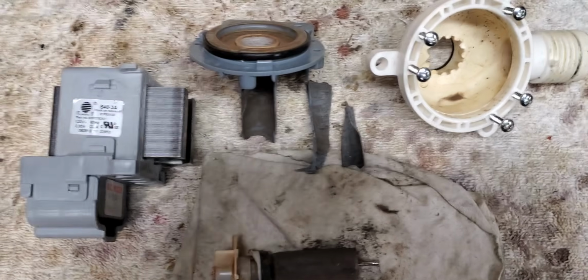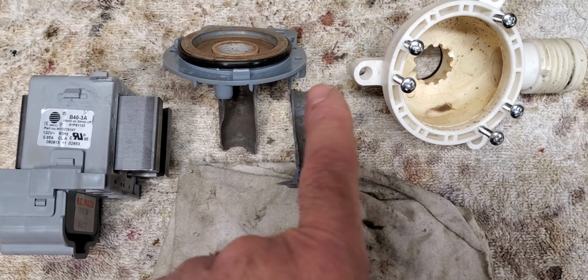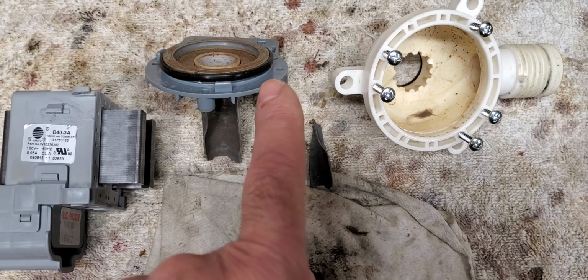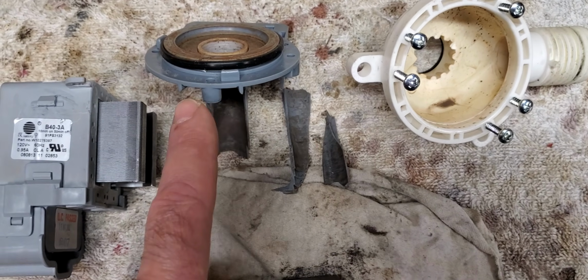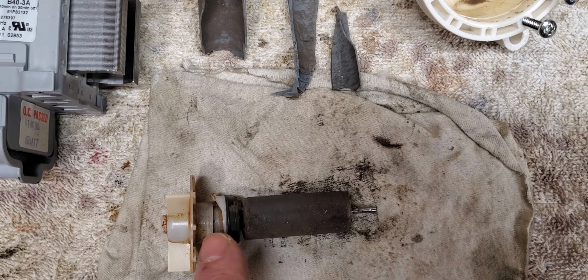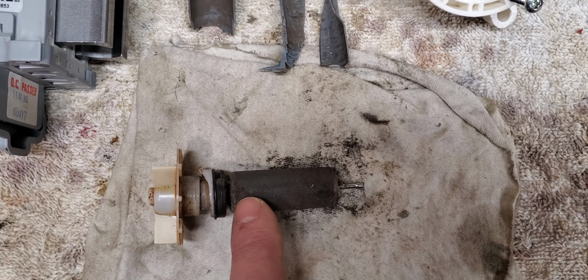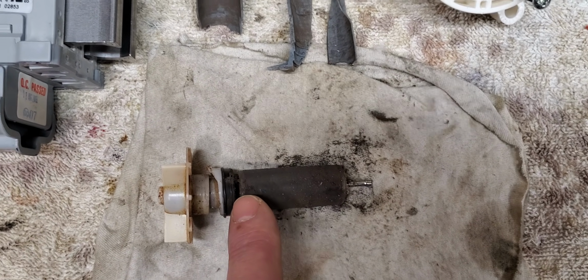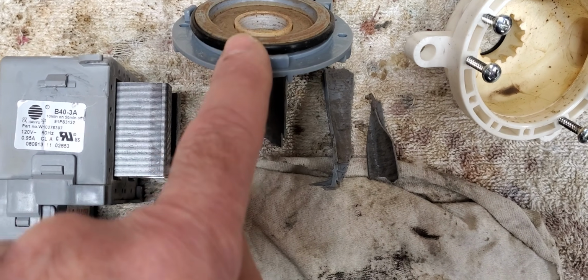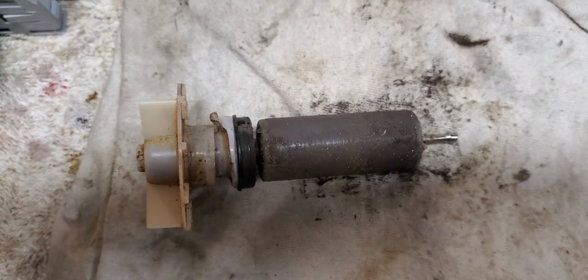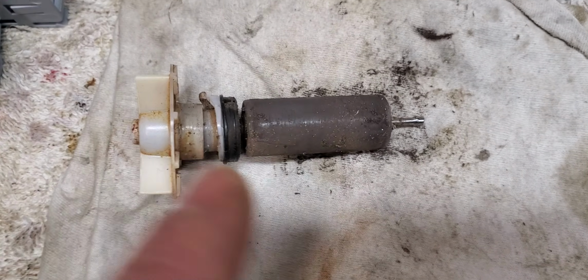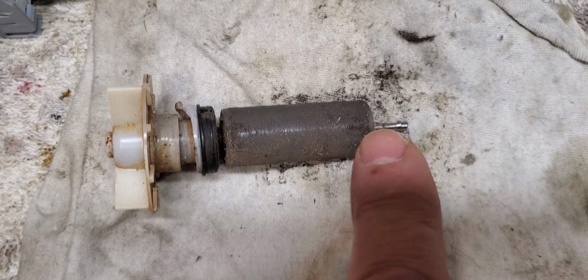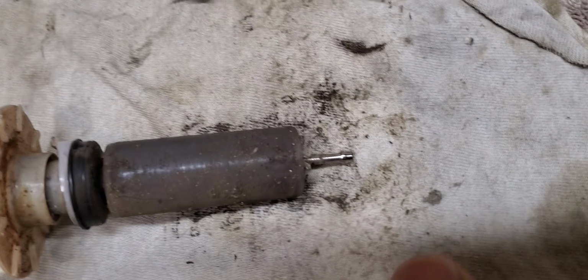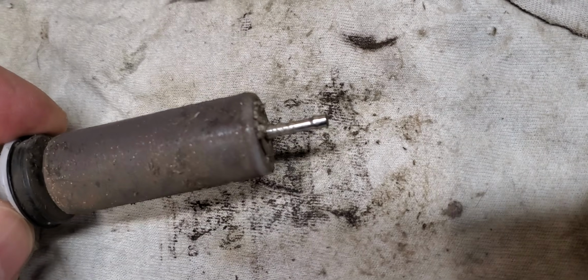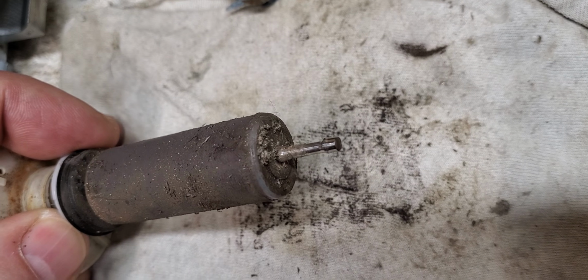Let me get the perfect zoom here. The pump is designed so it cannot leak to the exterior, and that's a great design - this is a nice pump. But there is a shaft seal on the impeller shaft that seals the magnet - this is a rotor, a magnet - and it seals from the water itself. You can see in my case the seal failed, and this whole cavity filled up with debris, rust and scale. It even looks like sand on the end here. That's the bearing, by the way - look how worn out that is.